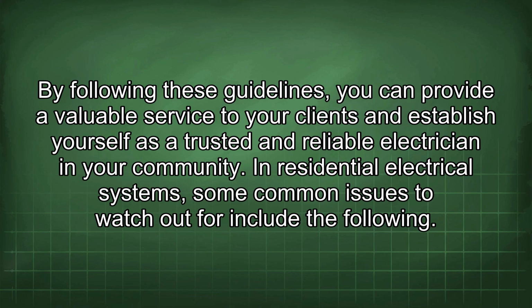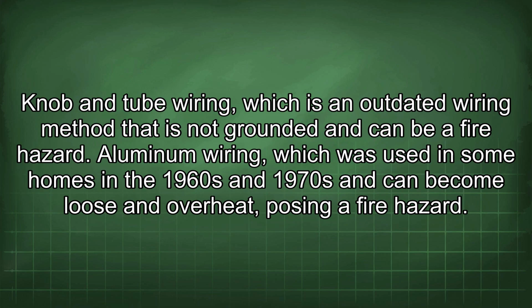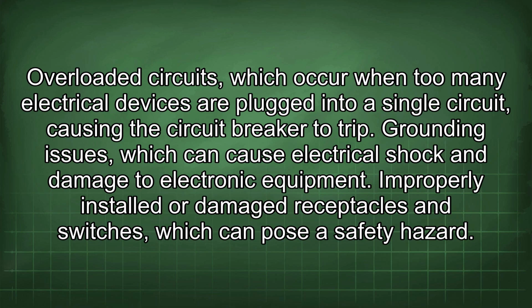In residential electrical systems, some common issues to watch out for include the following. Knob and tube wiring, which is an outdated wiring method that is not grounded and can be a fire hazard. Aluminum wiring, which was used in some homes in the 1960s and 1970s and can become loose and overheat, posing a fire hazard. Overloaded circuits, which occur when too many electrical devices are plugged into a single circuit, causing the circuit breaker to trip. Grounding issues, which can cause electrical shock and damage to electronic equipment. Improperly installed or damaged receptacles and switches, which can pose a safety hazard.